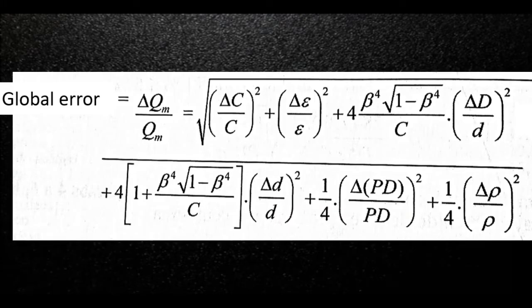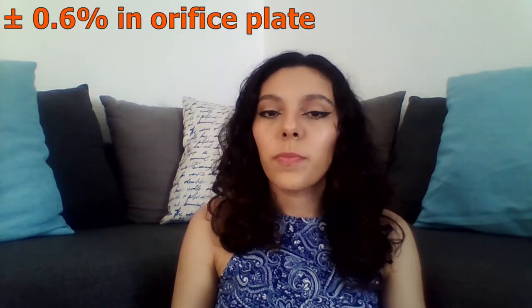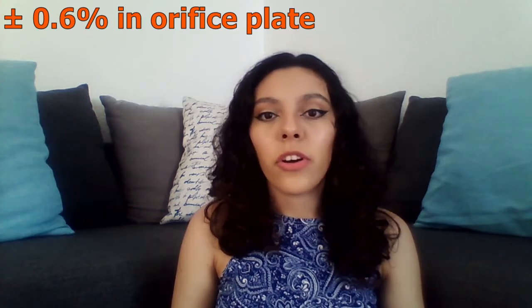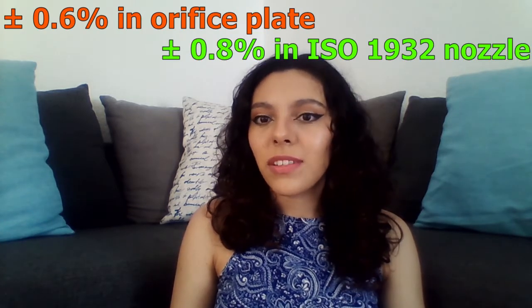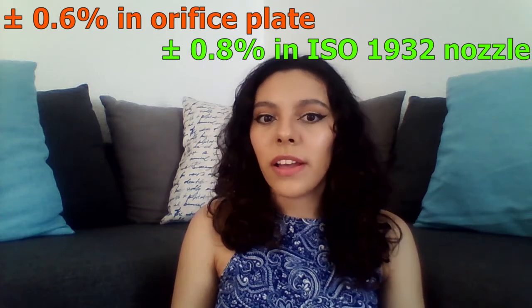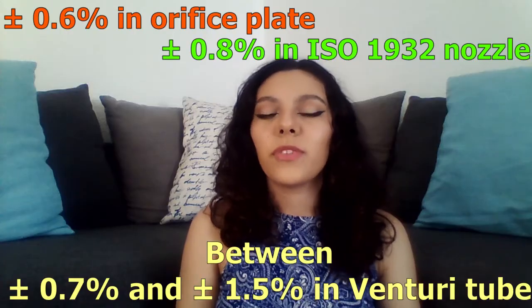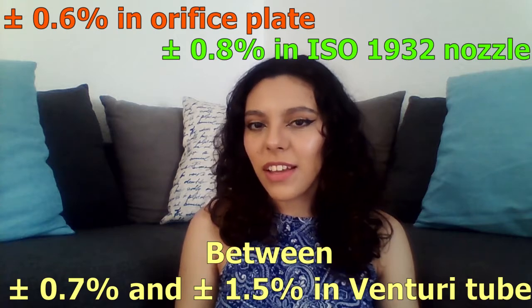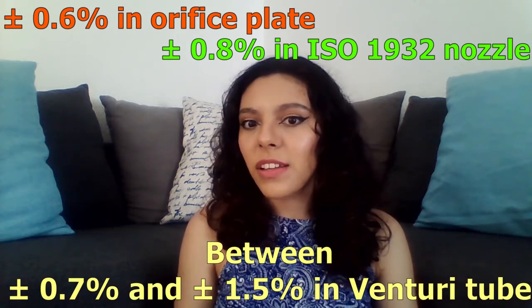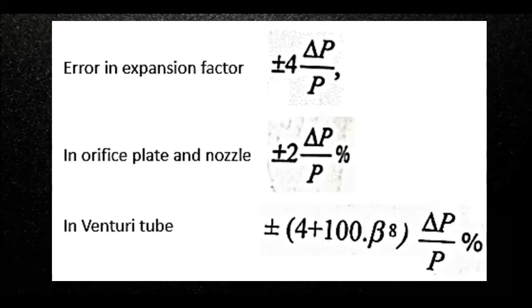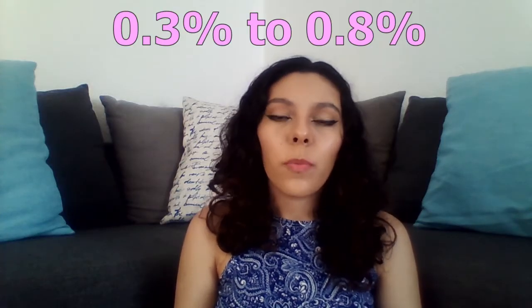To calculate the global error of the measure of a differential pressure object, we use this formula. The error in the discharge coefficient C is plus minus 0.6% in the orifice plate, plus minus 0.8% in the ISO 1932 nozzle, and between plus minus 0.7% and plus minus 1.5% in the venturi tube. The error in the expansion factor for each of these elements is this, and all of them within the beta limitations ranging from 0.3 to 0.8%.